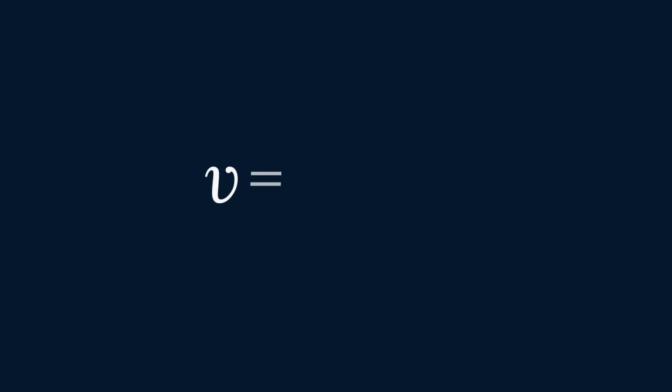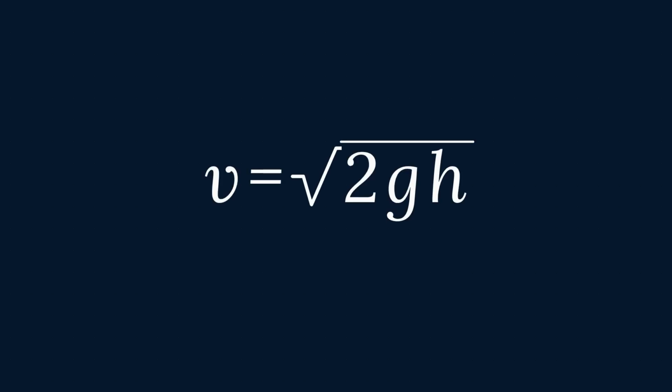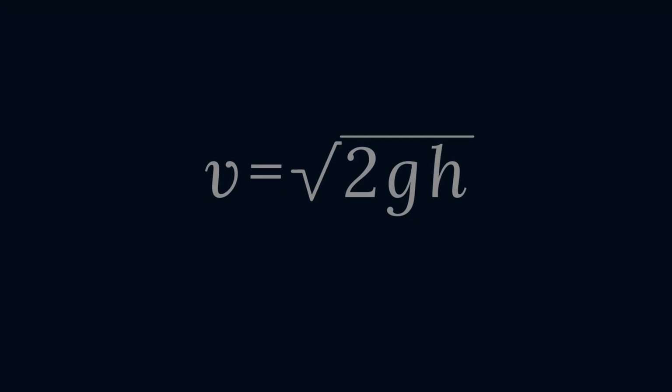height. This calculation assumes ideal flow conditions with no friction losses and uses Torricelli's equation, which relates flow velocity to the height of liquid above the orifice. The result helps engineers size drain systems and predict emptying times for storage tanks.